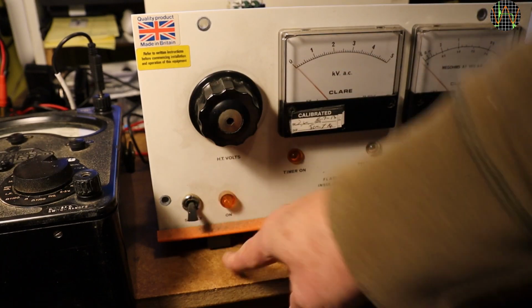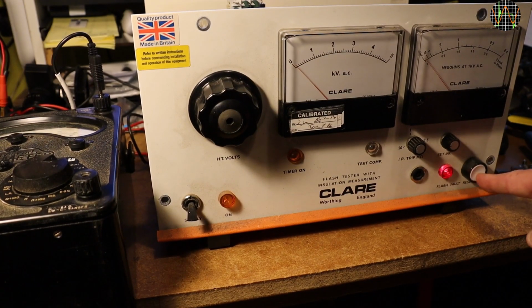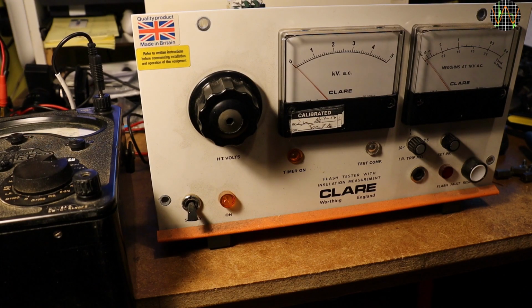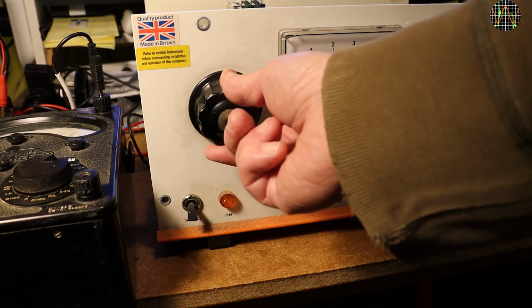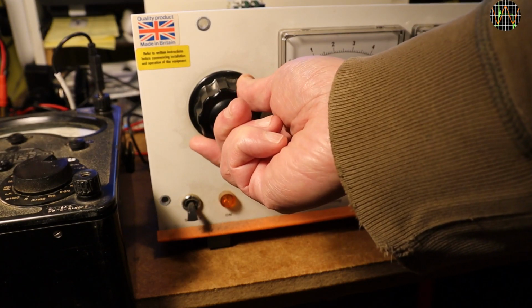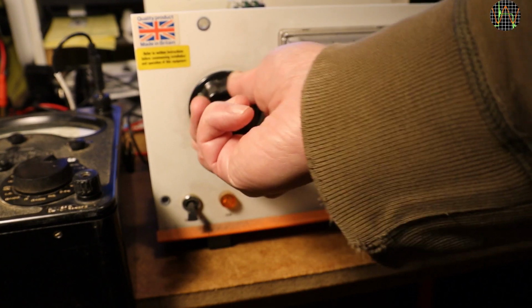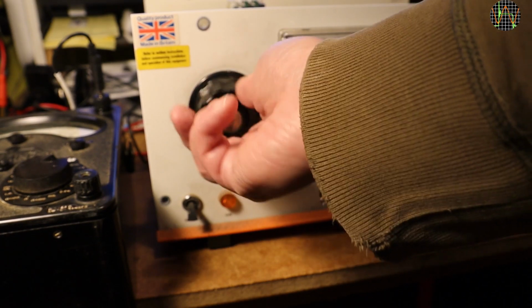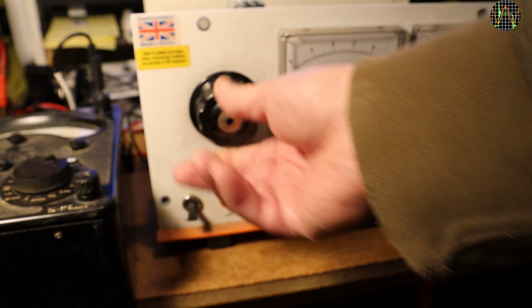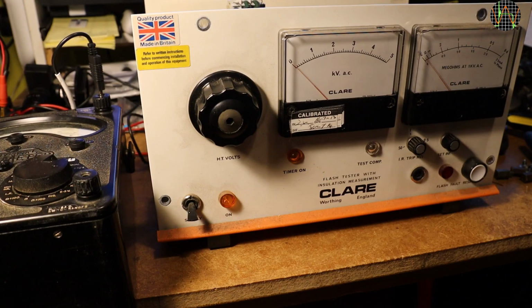Again, and this time I remembered the fault reset button. It did not work immediately, but finally the fault light is off and the buzzer quiet. Now I know what that round black thing next to the fault light is. It's a buzzer, and a very loud one at that. So the unit is now on and I try the voltage knob. Apologies for blocking the meter, but there was absolutely no movement. The needle stayed at 0 and the AVO meter confirmed there was 0 output voltage.